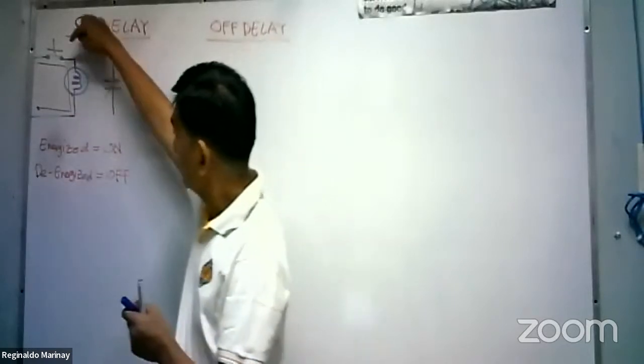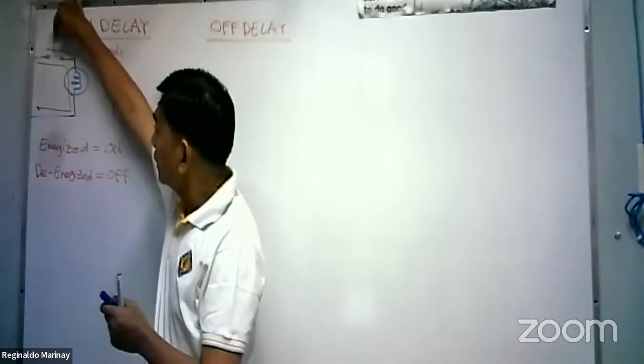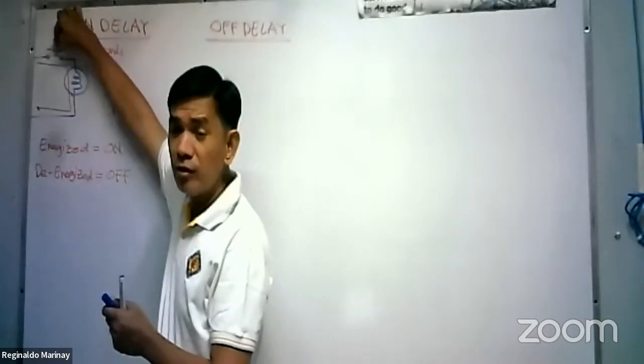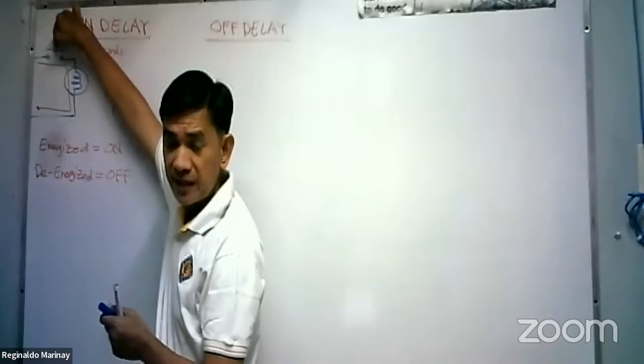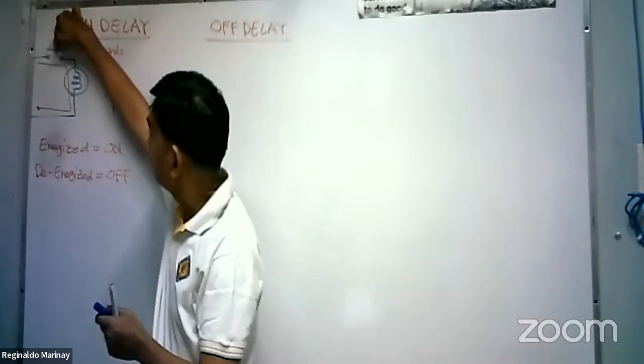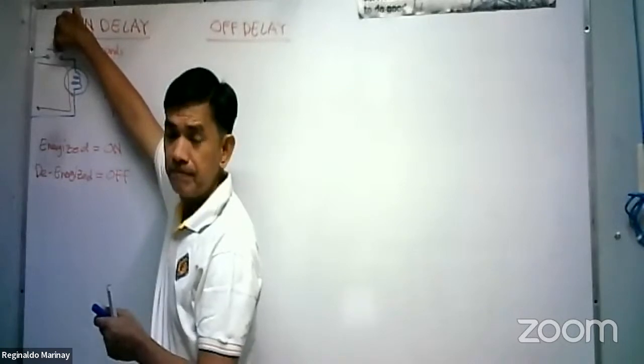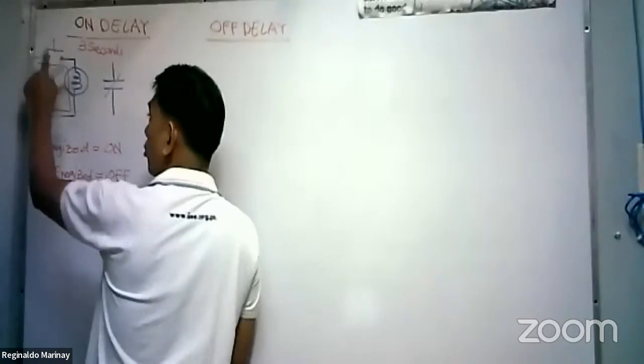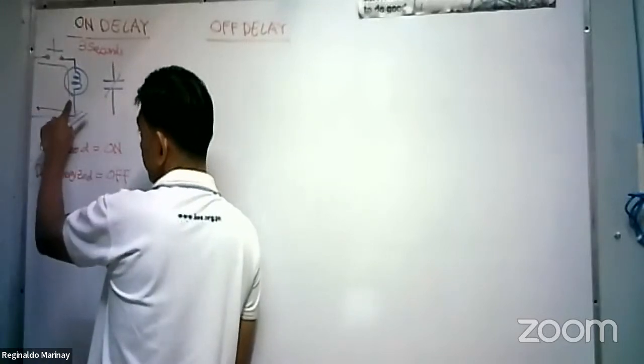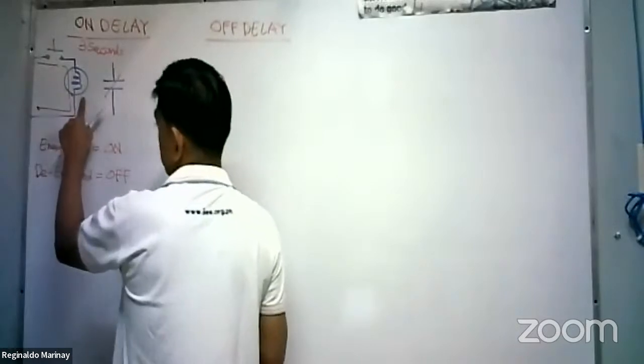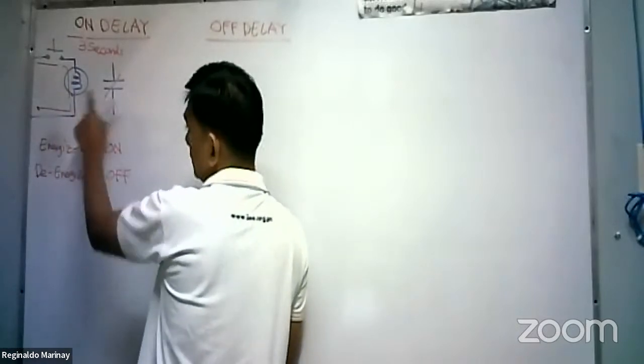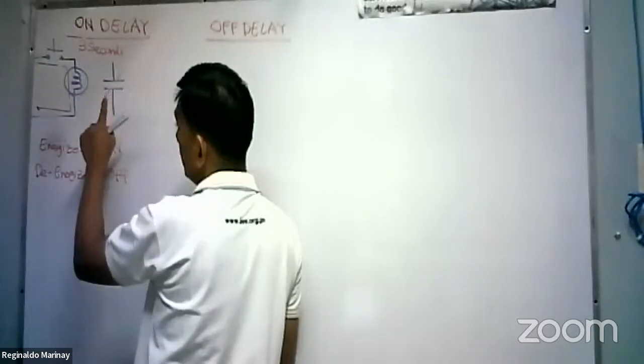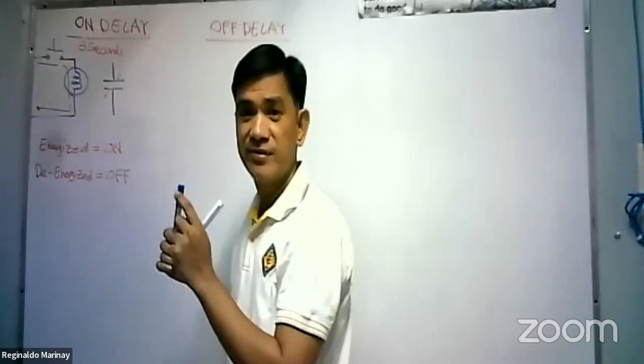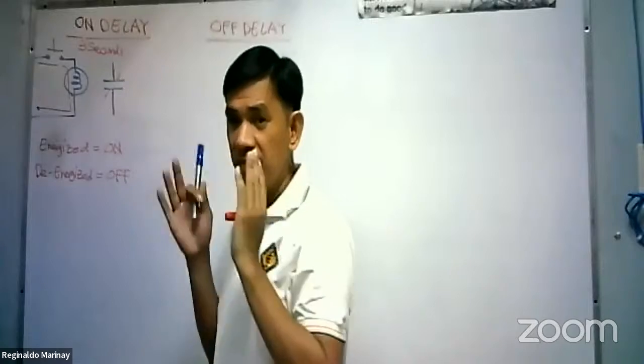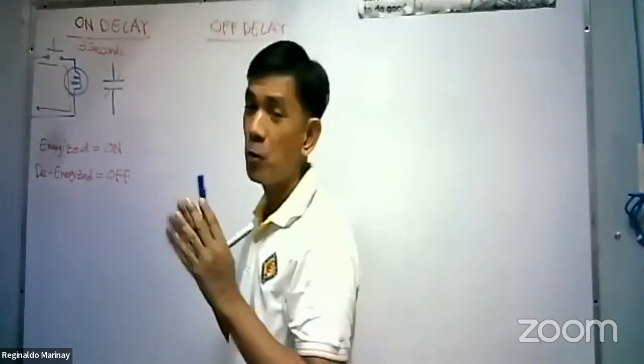As long as your finger is continuously pressing this push button, or you're holding this one, pressing it downward, this one. But once you release your finger here in the push button, this will become open and this will become de-energized, of course. That will become de-energized. Once this becomes de-energized, this will go back to its original position. Okay? So that will be the state of the on delay.